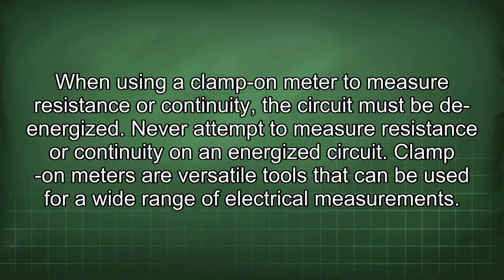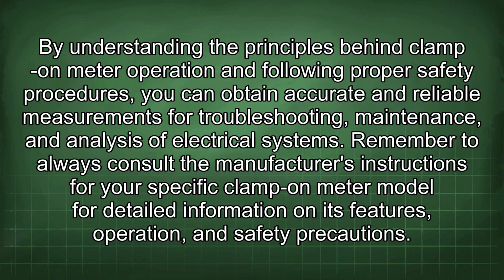When using a clamp-on meter to measure resistance or continuity, the circuit must be de-energized. Never attempt to measure resistance or continuity on an energized circuit. Clamp-on meters are versatile tools that can be used for a wide range of electrical measurements. By understanding the principles behind clamp-on meter operation and following proper safety procedures, you can obtain accurate and reliable measurements for troubleshooting, maintenance, and analysis of electrical systems. Remember to always consult the manufacturer's instructions for your specific clamp-on meter model for detailed information on its features, operation, and safety precautions.